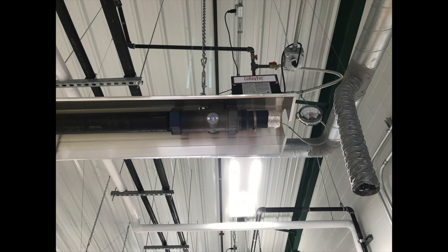Check the rotation of the pump, as it will create vacuum in both directions. We need to verify that the impeller is rotating the same way as the arrow on the scroll. Any other questions on CoRayVac SF heating systems?